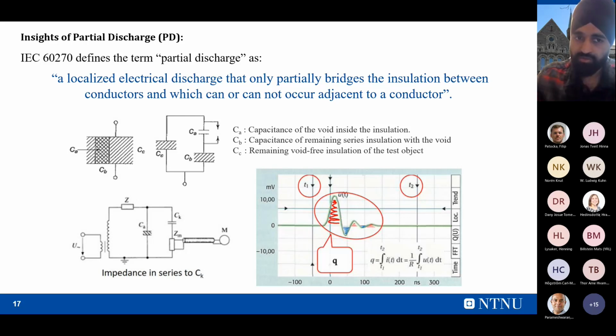So at that time the amount of charge is transferred from this capacitor to the void capacitance. Indirectly we measure that amount of charge: after discharge, the capacitor gives the charge back to the void to charge it again. So we measure the amount of charge indirectly from this capacitor externally. That gives the idea that these are the voids present inside the insulation, and we measure the amount of that charge.